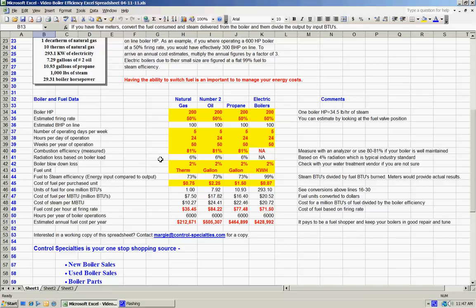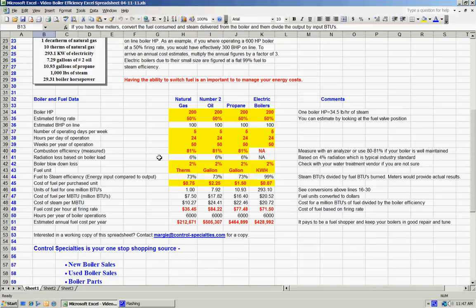The radiation loss figures that I've shown in line 41 are based on a 4 percent radiation loss for a new boiler and in good shape. The 6 percent figures here represent the radiation loss based on a 50 percent firing rate. There's quite a bit of math behind that, but if you'll just accept my figures for now, it's close enough to the real world.